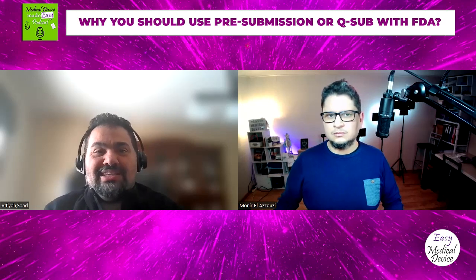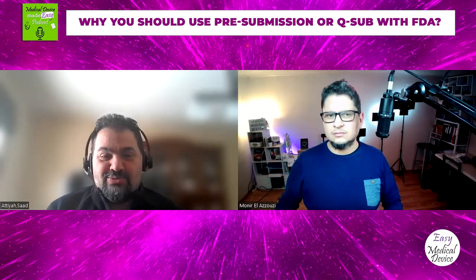Correct. So let's go back to a couple of questions that a company might have. You don't want to leave the door open for FDA to dictate the type of testing you want or need to do. For example, a bad question is: is biocompatibility testing required? That's a very broad question. Maybe you need to focus it on: we're proposing biocompatibility isn't required, and the why.